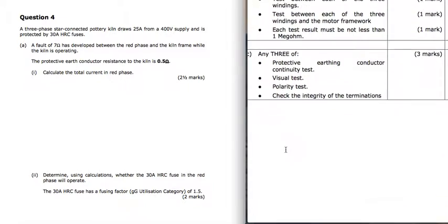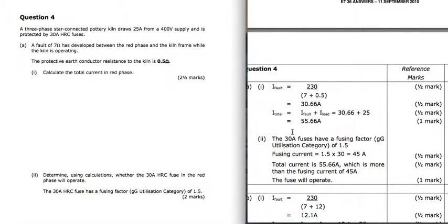Now the trick here is that the total current is going to be the normal current, the voltage divided by this fault plus this resistance here, and then the total current is going to be that fault current plus the normal current, so this 25 amps here. So to find the fault current, we do 230 volts, which is our phase voltage, because it's a star connected pottery kiln. So 230 volts divided by 7 plus 0.5, which gives us 30.66 amps. So that's the fault current. The total current in that red phase is going to be that fault current plus the 25 to give us 55.66.